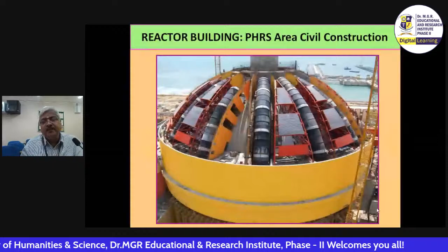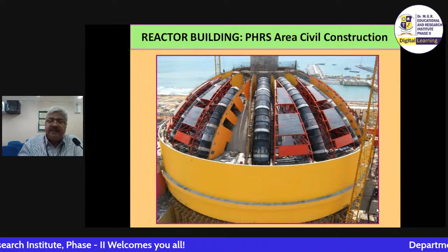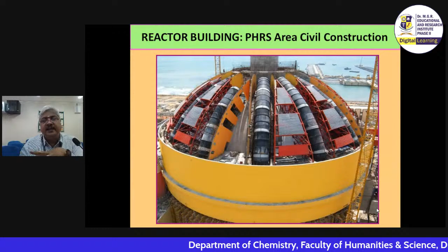During a blackout condition, the steam will come to this heat exchanger. Inside, the heat exchanger will be there, and that heat is taken away by atmospheric air. The hot air will go to the top, and the system will be actuated within that heat.